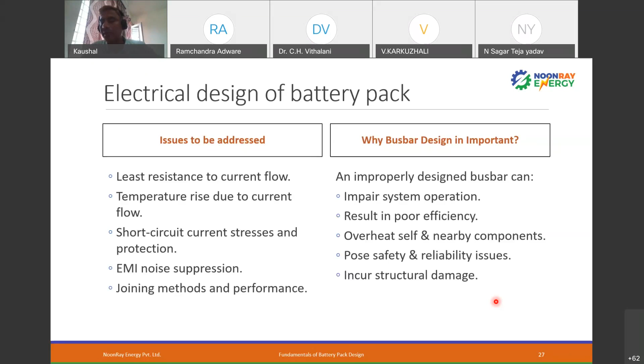Safety and reliability issue: if that is not controlled, what will happen? If the heat keeps coming continuously, it will melt that bus bar. Once melted, you cannot take out any current, and there is a possibility that a drop of the melted material can go somewhere else and lead to a short circuit. Because of that, there is structural damage. Now you have to completely open the battery pack, repair it, and only then can you use it.